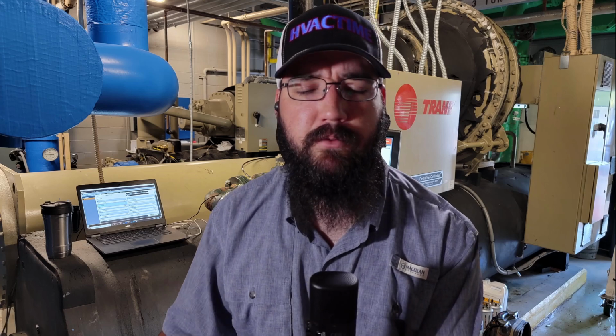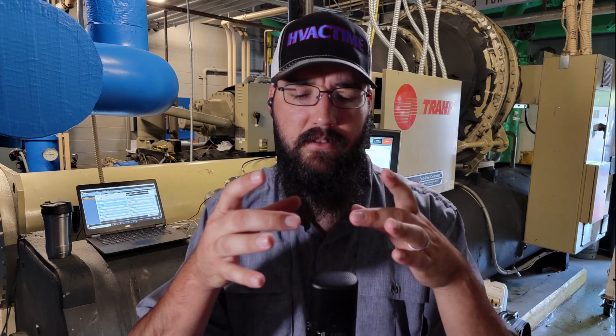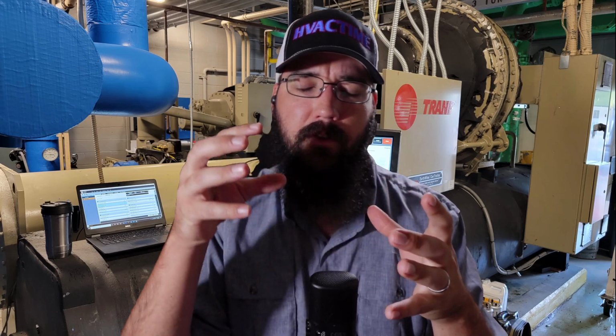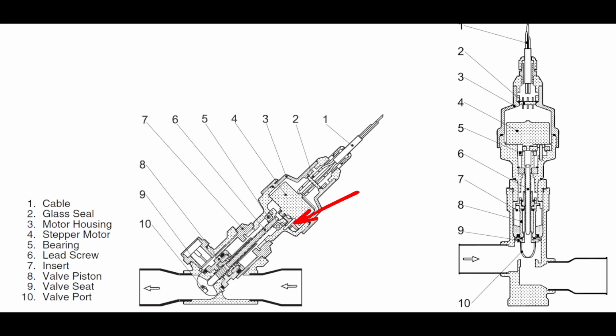But these smaller ones you may be used to seeing, the coils slide over the valve body. So you've got the valve body, and then you can take the coil off and on. That's one of the big separations you're going to see: we don't have a removable stator. That's what that coil piece is. That is your stator. That is fixed on these styles of valves. Even when they get far smaller than what I've shown you, that's going to be a very consistent theme.